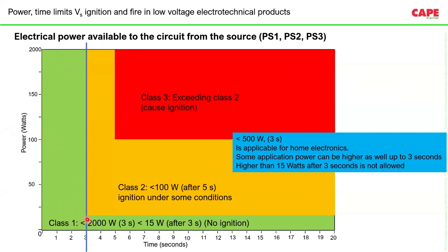Or if the heat dissipated is less than 15 watts, even for a longer duration, then the chance of ignition of fire from electricity is quite less. But limiting the heat dissipated to less than 15 watts is quite difficult. We have to have a power supply with limited current, which is another technique. But the simplest technique we can implement is to ensure that the device is able to disconnect within the recommended time. Similarly, the second concept is heat dissipation due to a fault. If it is limited within 5 seconds, then the chance of ignition is possible only under some conditions. Similarly, if the heat dissipation is limited to less than 100 watts, ignition is possible only under some conditions. If these limits are exceeded, of course, electricity is dangerous.